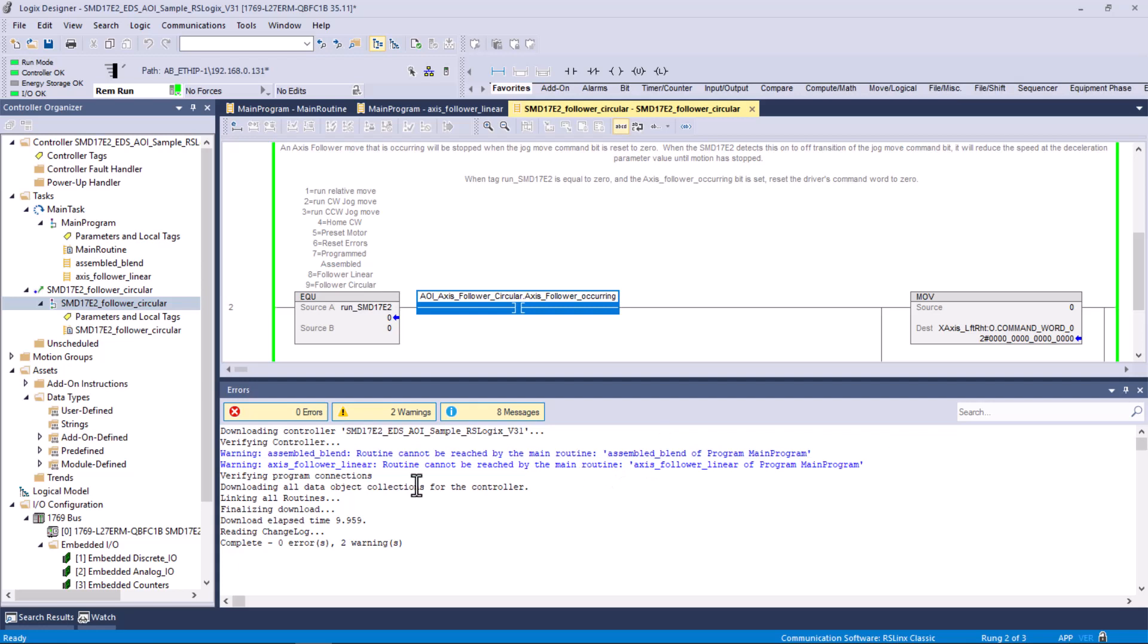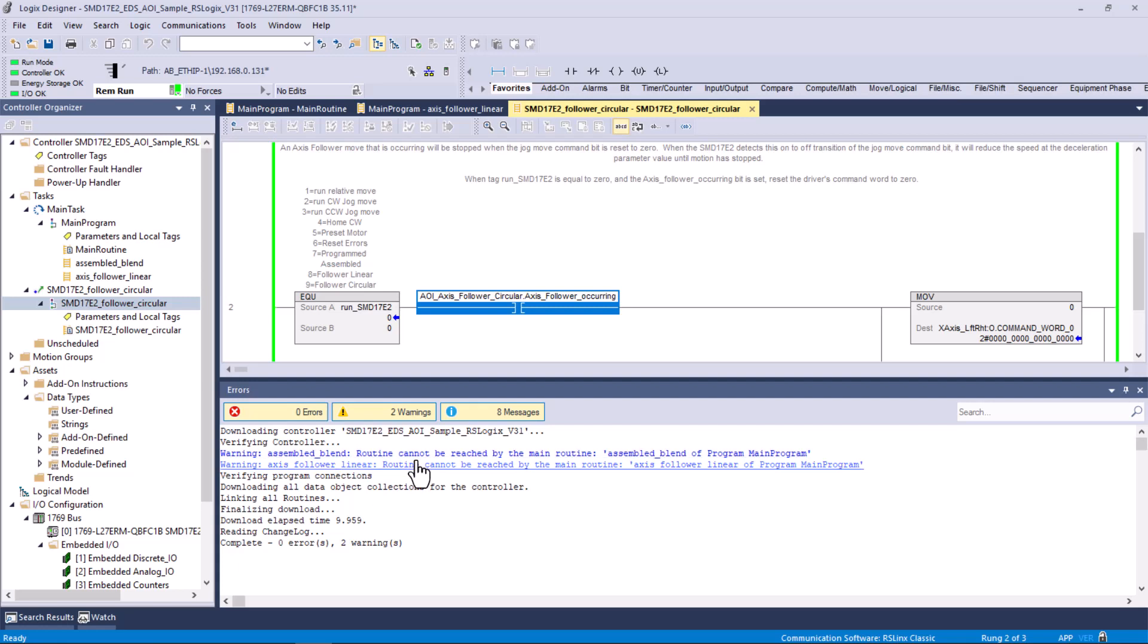I had it unplugged, so the controller wouldn't override the dashboard that we were using earlier. So now we download. I didn't notice that we had a couple warnings, and actually this is fine. We don't want to execute those two. What it's saying is that in the main routine, there are no JSRs that jump to assembled blend or axis follower linear. But as far as errors go, there were no errors. Now we're online in the run mode with the unit.